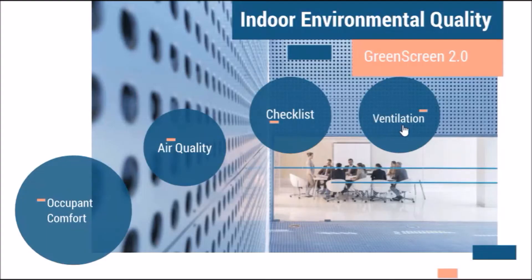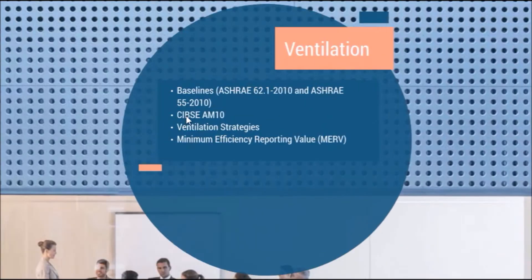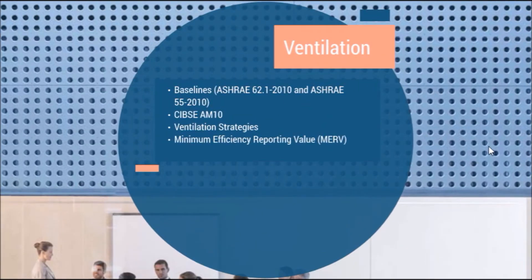Let's head into ventilation strategies first. This is the first step usually — it's about air exchange, introducing fresh air into the building. This is measured in cubic feet per minute. Building codes usually require 15 to 20 cubic feet per minute per occupant. Our baseline is established from these standards.